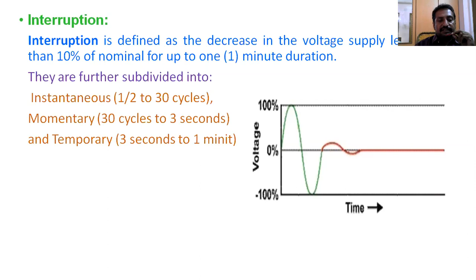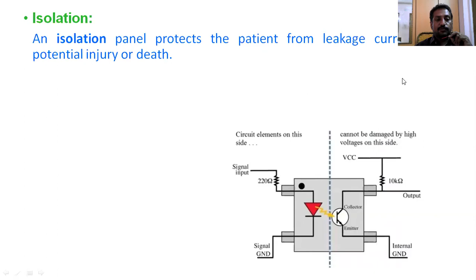Next, isolation. Very important. An isolation panel protects the patient from leakage current and potential injury or death. When you have a bus bar, all the equipment should be isolated. You see here, there is circuit equipment on this side and circuit equipment on this side. Otherwise, due to any leakage current flowing through one circuit, it will affect the other circuit. So we want to isolate the equipment connected on the panel. Otherwise, there is leakage current and potential injury or death.